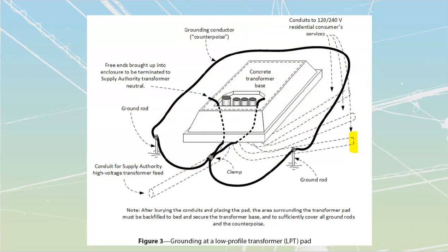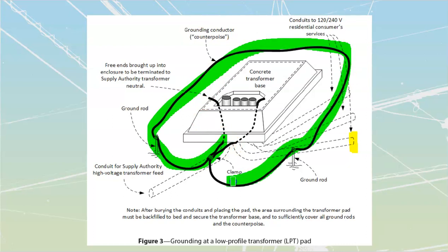What we do is we place around there this component over here. Now this is a heavy steel cable that is heavily zinc coated. Super stiff cable. You're going to run the thing all the way around the transformer base, and then you're going to run up the free ends inside, and you're going to deke them just out of those two corners over there. You're also going to apply a clamp. It is a big bolted clamp across over here to tie those together, and then you're going to clamp it to two separate ground rods.